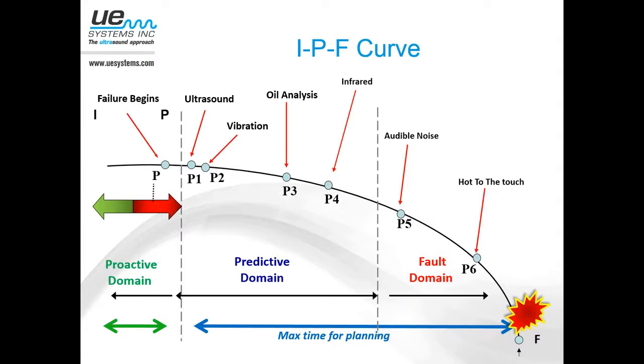And that's where you've already got faults. What I really like about this curve, and I like to bring this up whenever I talk about any condition monitoring technologies, is that while we can detect failures fairly early using ultrasound and vibration, we don't want to become very great failure finders. And I hear this all the time. I hear people say, we've got a great vibration program, or we've got a great ultrasound program. We find all these failures. Every month our guys are coming up with great finds. Well, okay, that's good that you found them before you were down here in the fault domain. You found them early, but now what do you do with that information? That's the key to the whole thing.